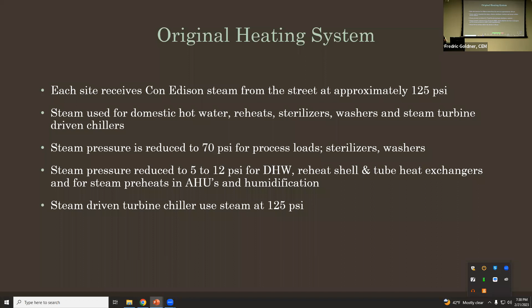We took that 125-pound steam, dropped it down to 70 pounds for our sterilizers and washers and other process loads. And then also took that steam and dropped it down to 5 to 12 pounds for domestic hot water, our reheat systems through shell and tubes, and our steam preheats in air handlers and humidification. And then we had steam turbine driven chillers using steam at 125 PSI. With that old system, it was wasteful. It was costly.